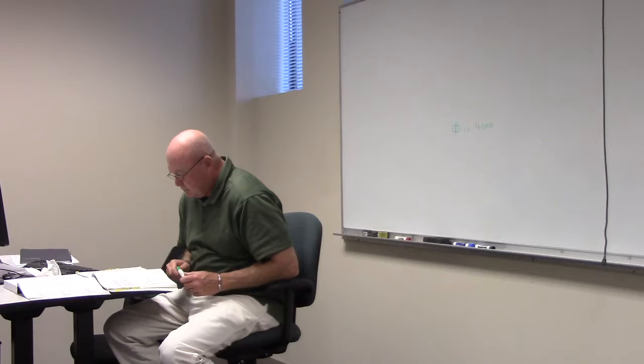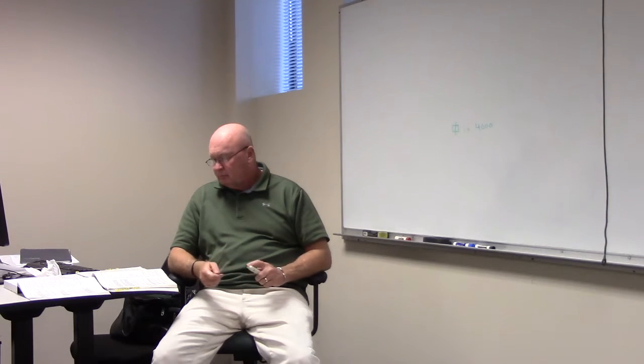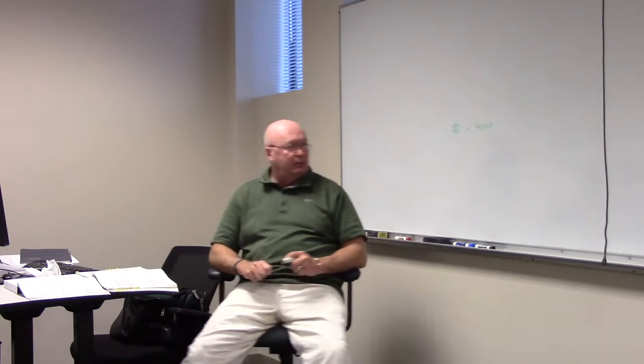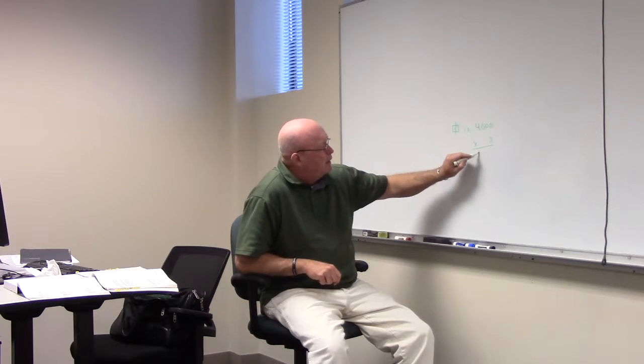So we go back to table 220.12, and we see that for a retail store, how many volt-amps per square foot are we going to use for lighting? Table 220.12, for a store. Number 3. So we're going to take 3 and multiply it times what? 4,000. All right, we're going to get 12,000.